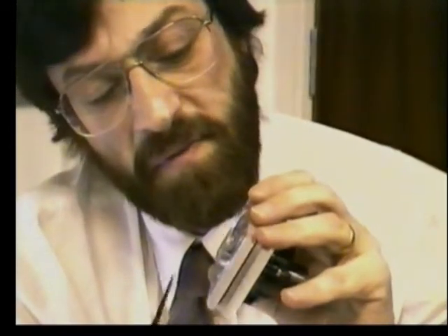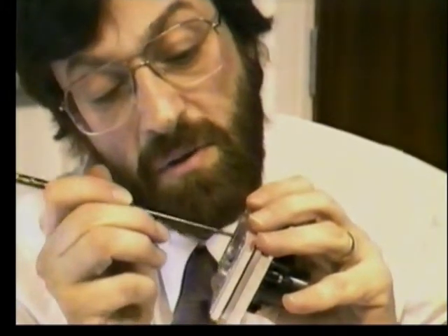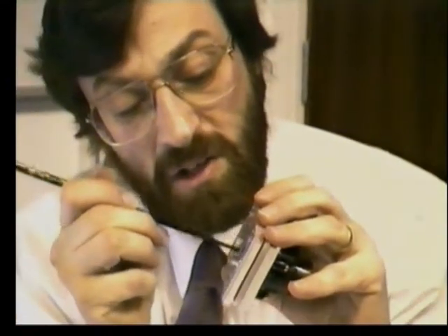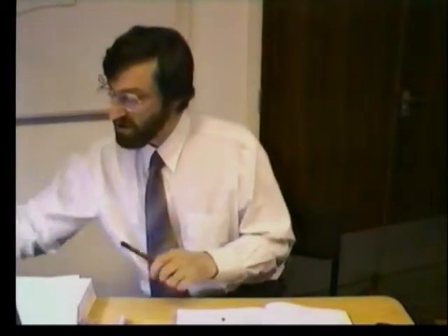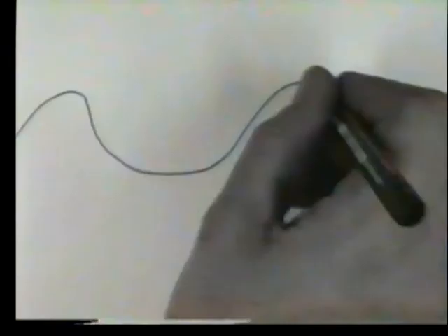So what we've managed to do is we've transduced flow rate into units of volume, into rotation, into a changing magnetic field, and if we have a simple guitar pickup here, what we're going to get out is we will receive along out of the transducer, as it rotates, hopefully a nice, won't be that perfect, pulse train.